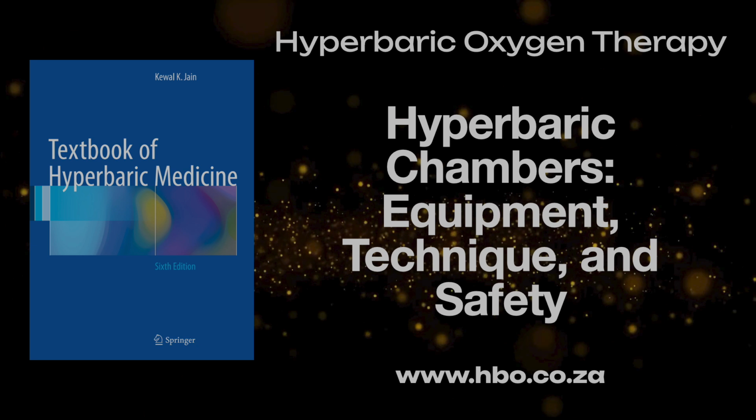So what are the main reasons to use these big chambers? Well, treating many patients simultaneously is obviously huge, especially for things like disaster response. But maybe even more importantly, they're essential when you need doctors or special equipment inside with the patient. Like a pressurized operating room. In some cases, yes, or for intensive care. And, as we said, the fire risk is much lower because it's pressurized with air.